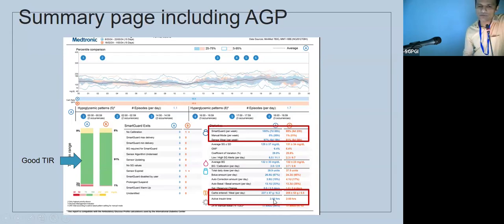Then you also see what carbs were entered and what is the active insulin time. It also gives a lot of other readings like average glucose, GMI, that is glucose management indicator, considered the equivalent of HbA1c, the variability in terms of CV, and the average BG. Here, average SG is average sensor glucose, and average BG is the blood glucose that was entered as calibration readings. Then it gives total daily dose, bolus amount, auto correction amount, auto basal or total basal amount per day, and the reservoir changes. So this data is important to make interpretations out of this analysis.